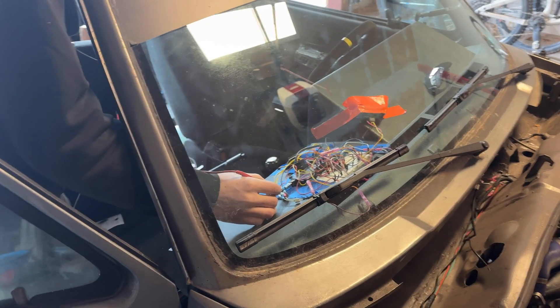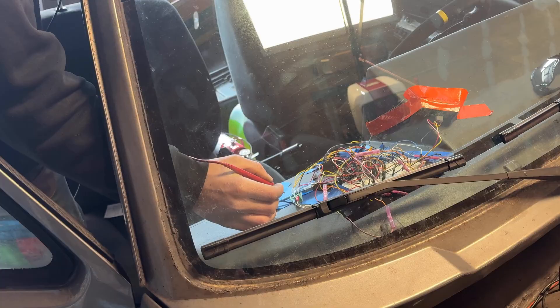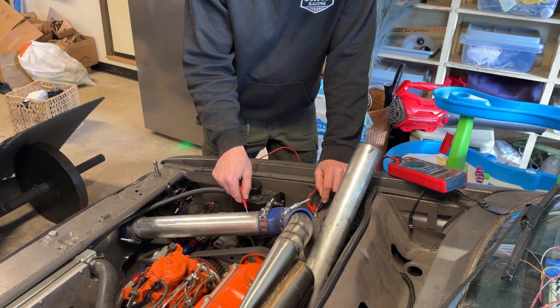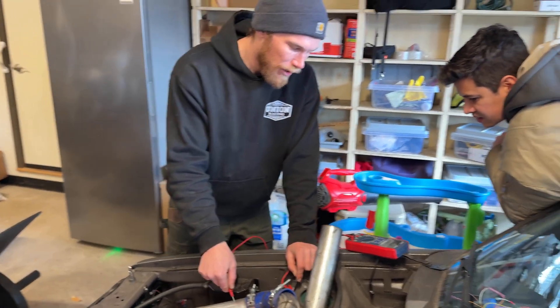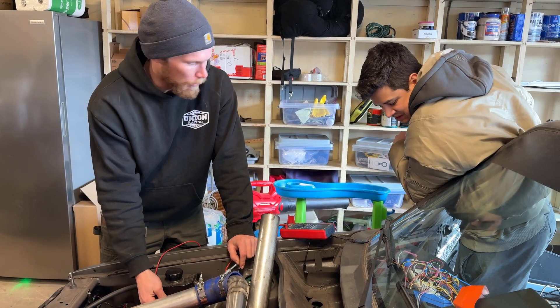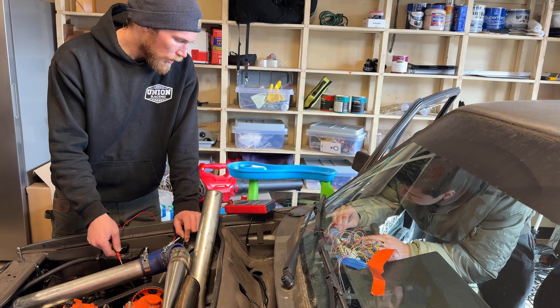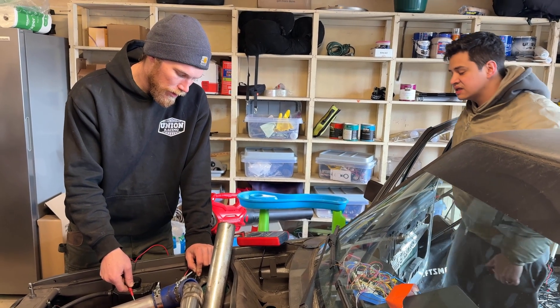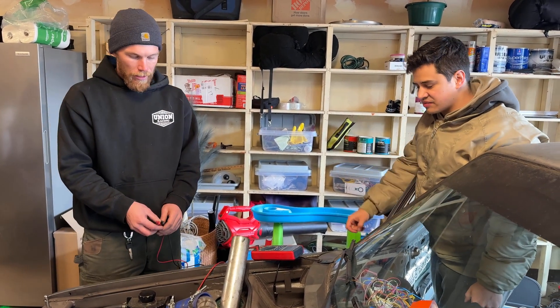The negative side is 1.6. I don't know how this tube is electrically grounded because it's floating in space on silicon tubes, but it might be grounding through the thermocouple wire because it snakes through. Now we're at 3.8, so there is interference — that means the thermocouple is touching that metal.